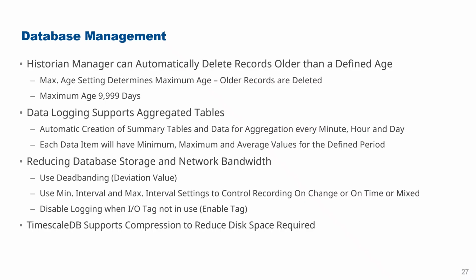Another option you've got there is minimum interval and maximum interval settings. So you can control recording on change or on time or mixed. You can record on change, you can use a dead band, but you might also say, well, I'm worried that if the value stays at around 50%, I might not see a change for some time. So you could set a minimum interval and record every 5 seconds, regardless of whether it's changed or not. That's in addition to on change, or maybe instead of it. Maybe you only want to record every 5 seconds, so you just use that minimum interval rather than on change, and then you could say record every 5 seconds.